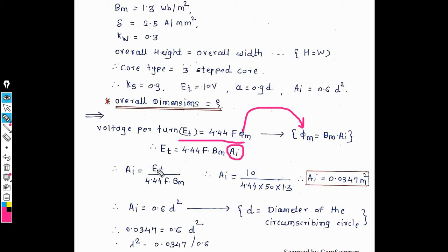Using the EMF equation: ET = 4.44 × f × Φm, and Φm = Bm × Ai, we substitute to get ET = 4.44 × f × Bm × Ai. Rearranging for Ai: Ai = ET / (4.44 × f × Bm). Substituting all known values gives us the net iron area Ai.